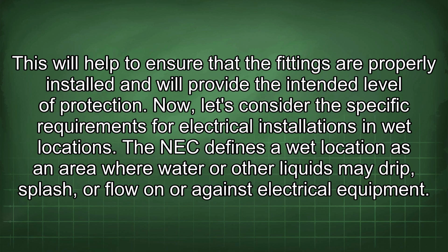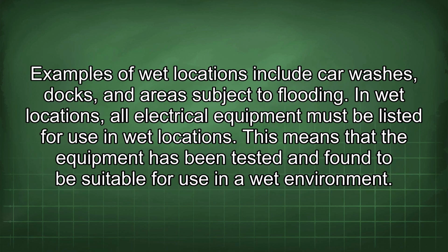The NEC defines a wet location as an area where water or other liquids may drip, splash, or flow on or against electrical equipment. Examples of wet locations include car washes, docks, and areas subject to flooding. In wet locations, all electrical equipment must be listed for use in wet locations. This means that the equipment has been tested and found to be suitable for use in a wet environment.